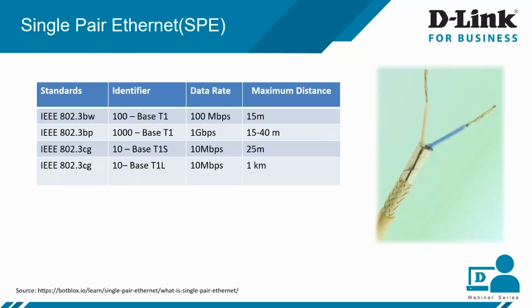Single pair Ethernet with power over data line provides power to the Ethernet sensor or endpoint over the same twisted pair, with the amount of power delivery determined by the length of the cable and the wire gauge. For example, at the maximum length of 1000 meters using 14 AWG wire, the IEEE specification allows for 60 volts and 13.53 watts of power at the endpoint.